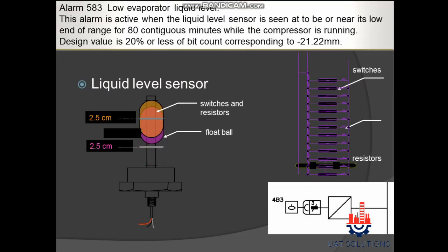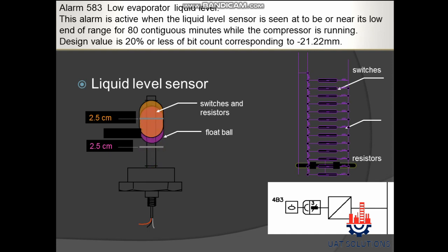Alarm 583 — Low Evaporator Liquid Level: This alarm is active when the liquid level sensor is seen to be at or near its low end of range for 80 contiguous minutes while the compressor is running. The design value is 20% or less of bit count, corresponding to minus 21.22 millimeters.